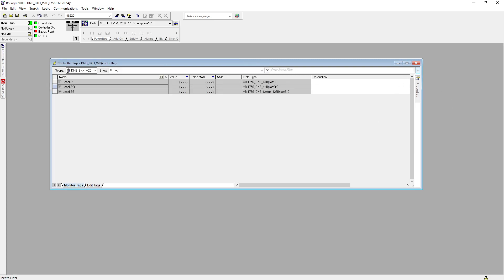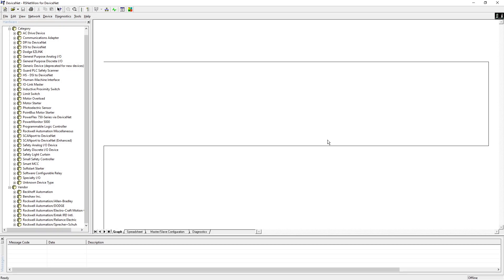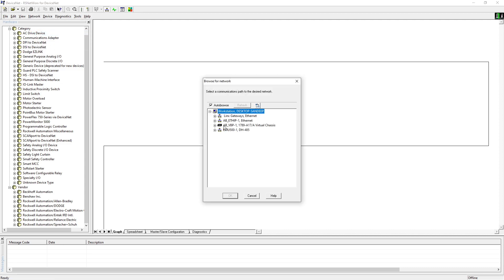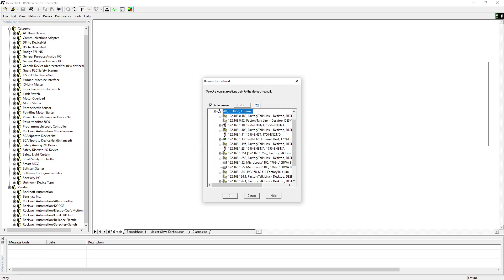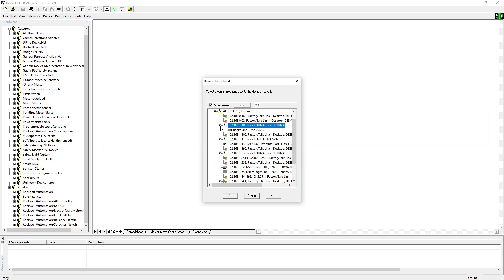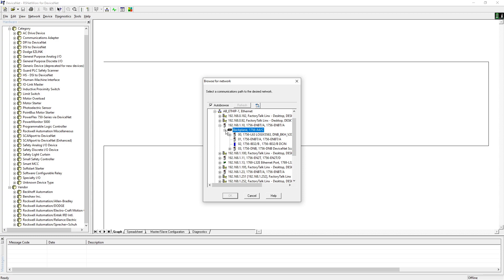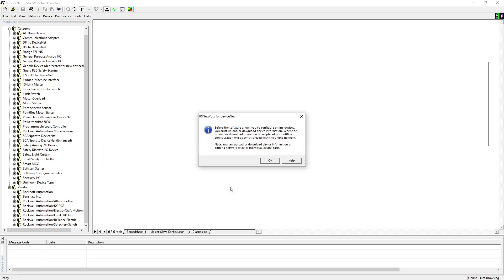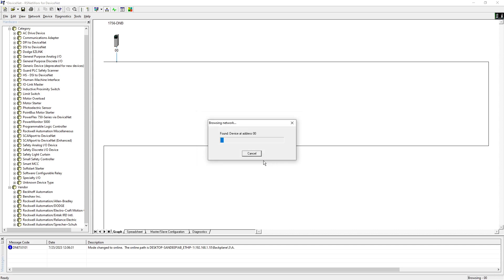To configure it, you open the DeviceNet RS Networks and I will go online. I will find where my module is, which is at 192.168.1.10. I will go through the backplane - this is my processor, my Ethernet card, my input card, and this is my DeviceNet card. Right now you can see it's grayed out because I need to expand this and go into DeviceNet, then I will hit OK. It will start browsing the networks or devices available over the network. So we have to wait until it will scan.